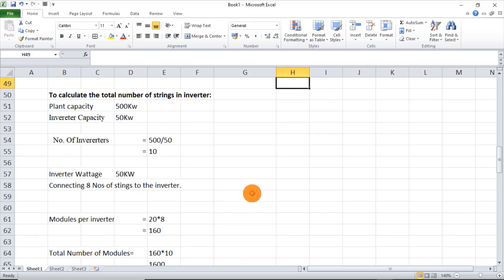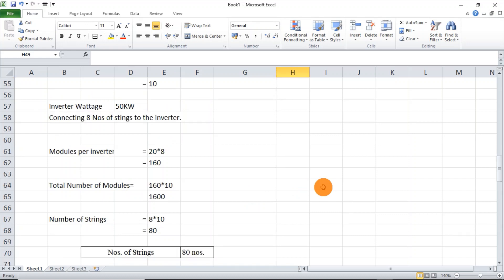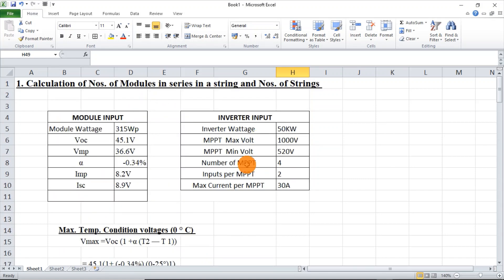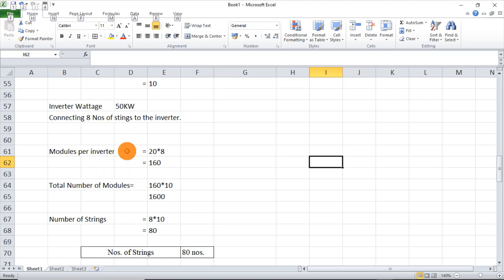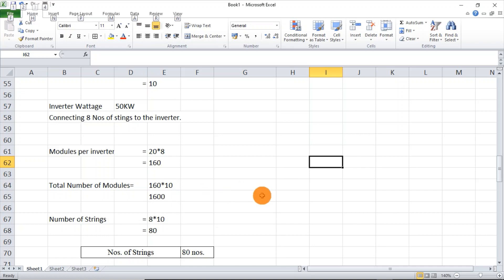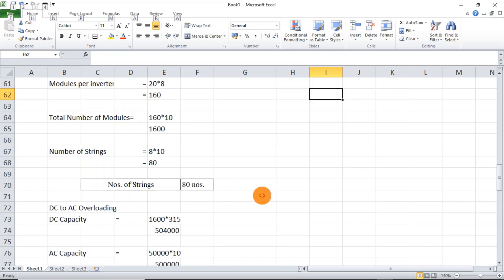Going with the number of modules and strings connected overall: we have connected 8 number of strings. You can see 4 MPPTs and each MPPT has 2 inputs, so the total number of inputs is 4 × 2 = 8. So we can connect a maximum of 8 strings to one inverter. That gives 20 modules × 8 strings = 160 modules per inverter. With 10 inverters, overall 1600 modules will be connected in the plant, giving 80 total strings.